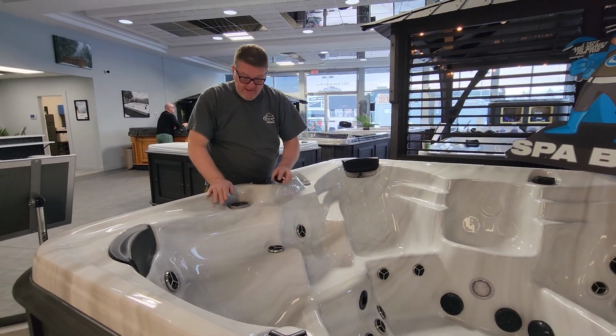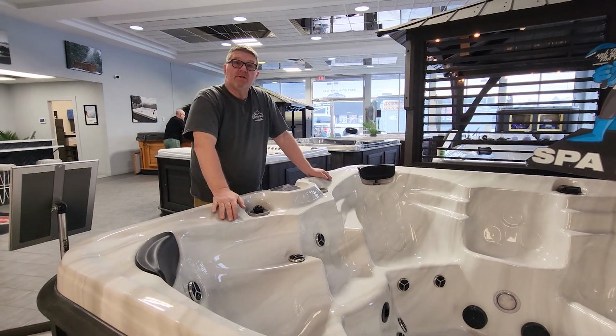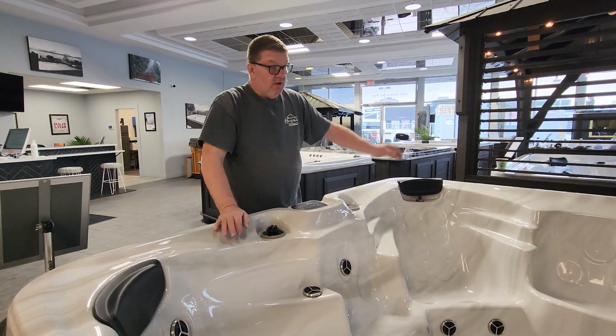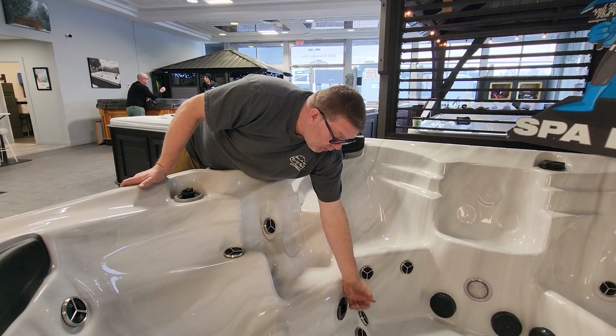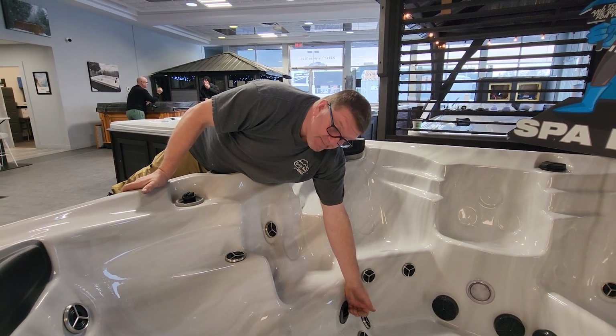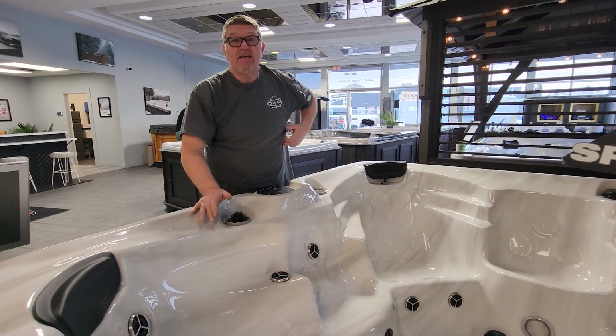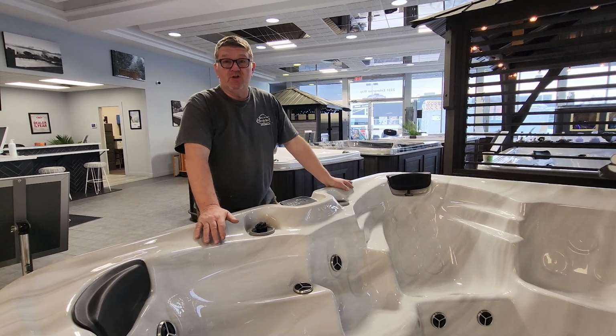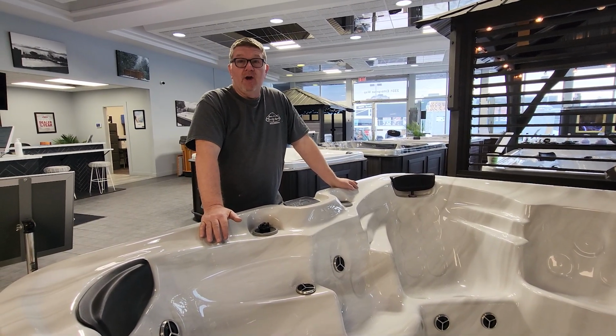A good feature is that every 2 or 3 months, whilst your tub is full of water, you should get a hose pipe and point it into the receptacle where the probe is, giving it a blast of water to keep it as clean as possible, because things will try to congregate around the probe.